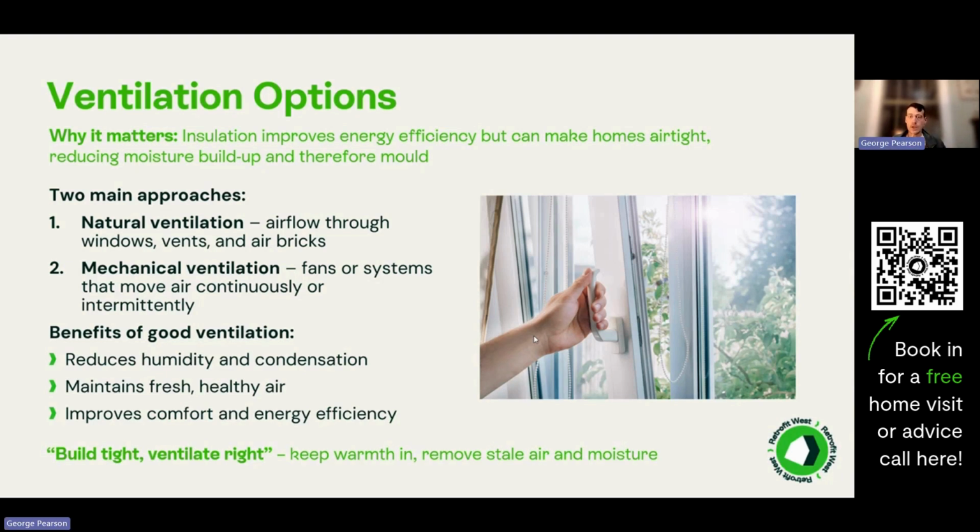Natural ventilation works when you can provide airflow through openable windows, trickle vents, and subfloor air bricks. Creating cross flows between two windows can be an effective way to purge internal stale air. Things can also include gaps and cracks around windows, doors, and floors, particularly if you have open suspended timber flooring. With original timber floors, there are normally lots of gaps which allow for air leakage and infiltration, as do chimneys and open flues. All these things create uncontrolled ventilation.